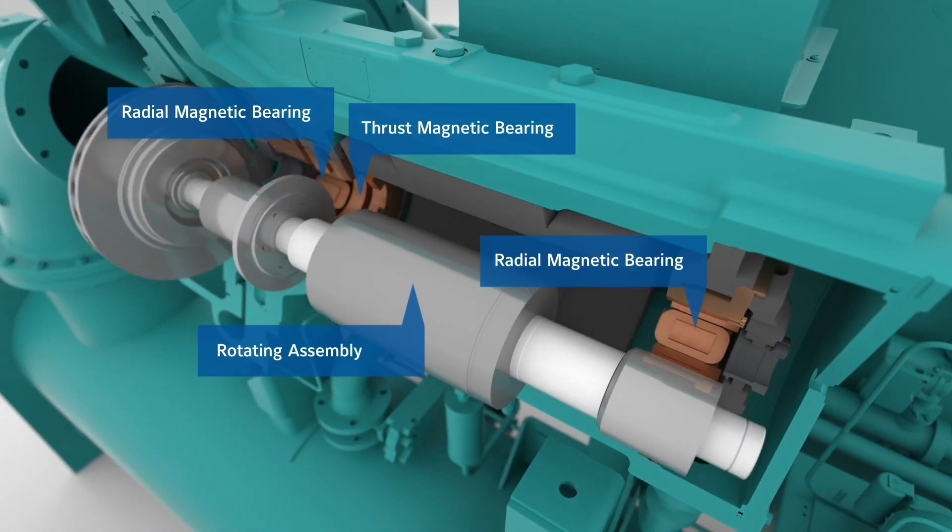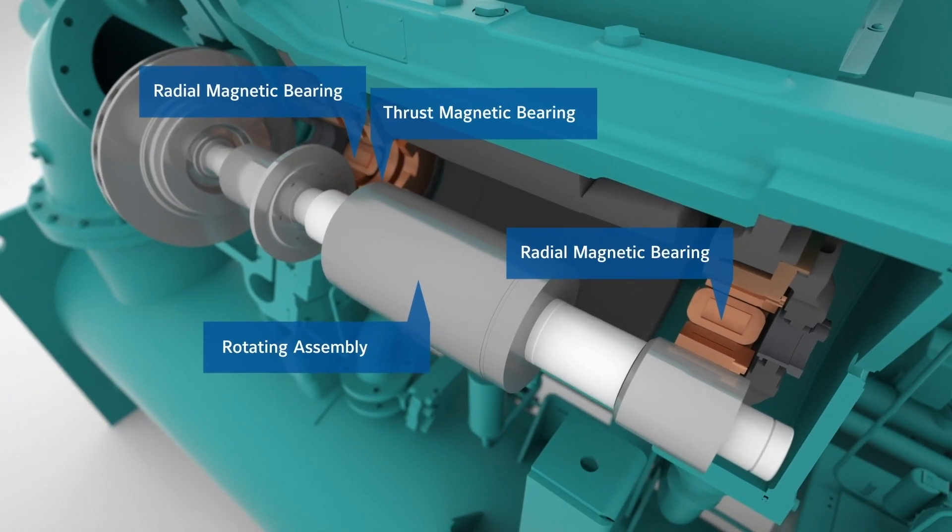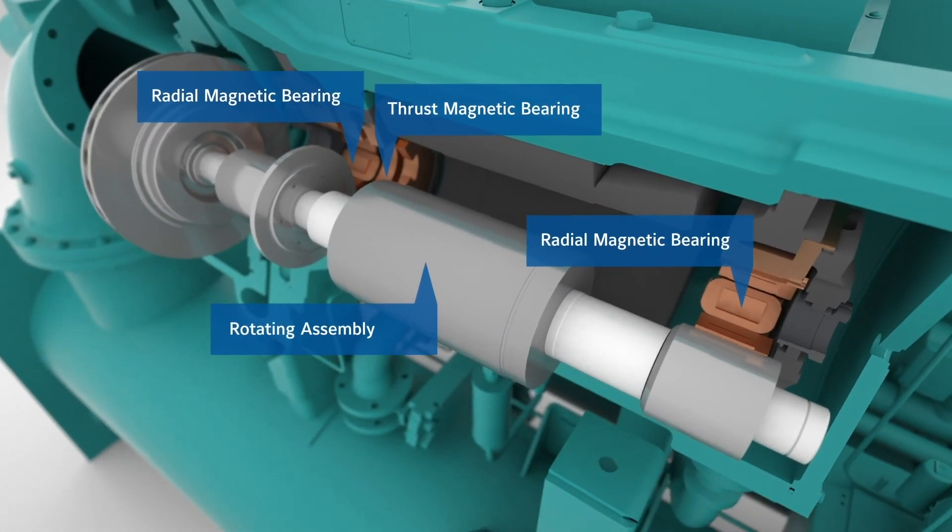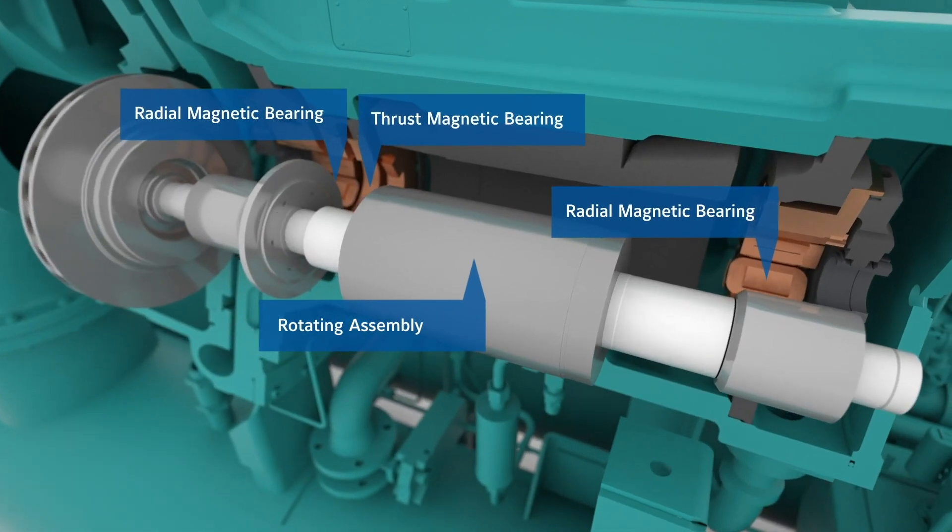The magnetic bearing controller is giving commands to the radial and thrust magnet bearings to ensure proper position. The controller can sense the position of the rotating assembly down to one one-thousandth of a mil. One mil is slightly less than the thickness of a human hair.